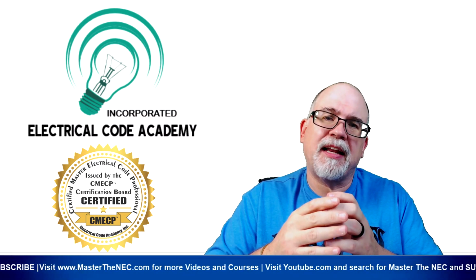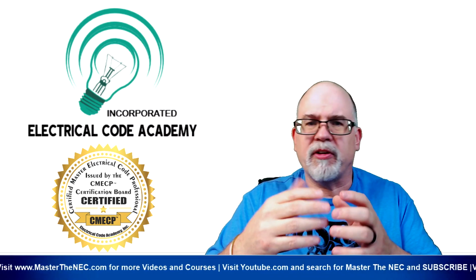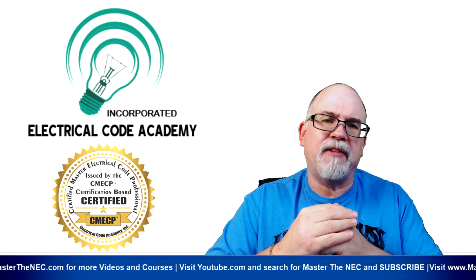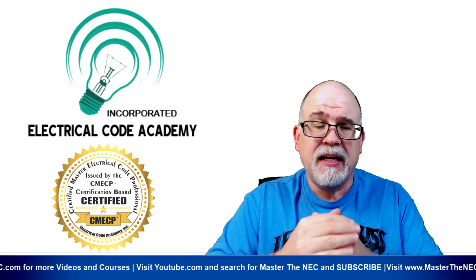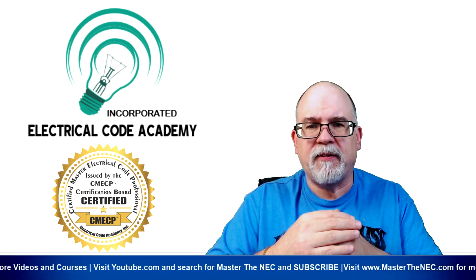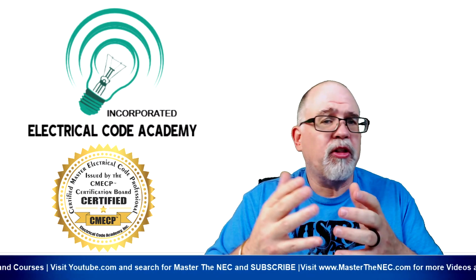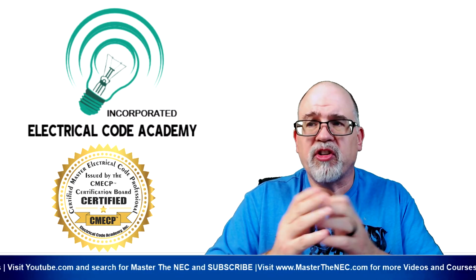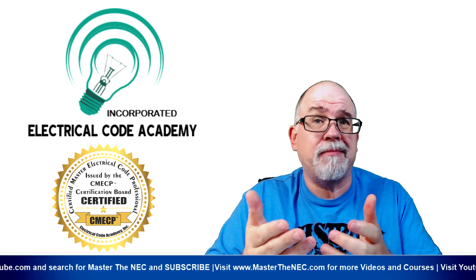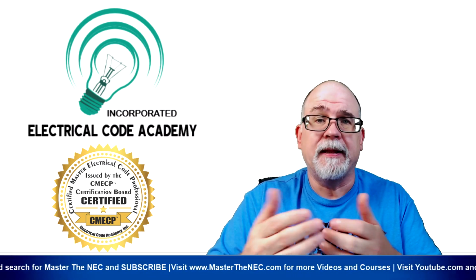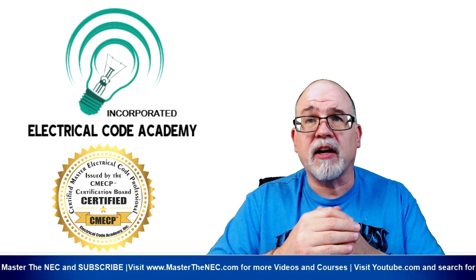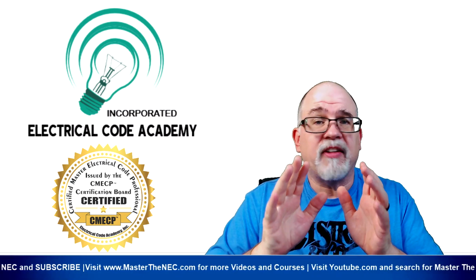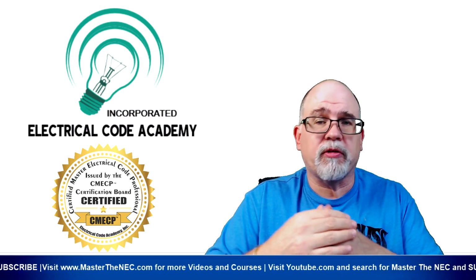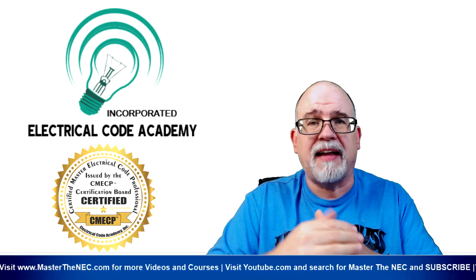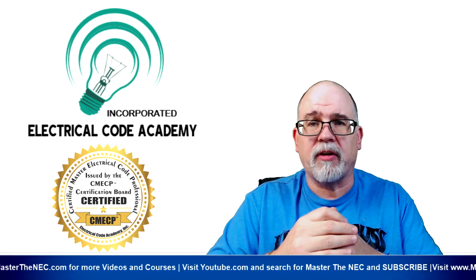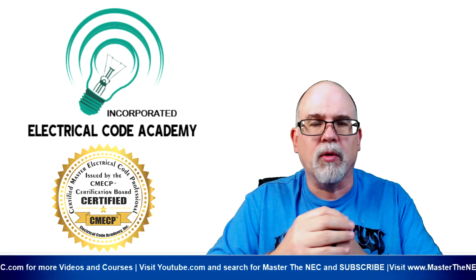I gave you some examples here of how they might work out for you in this scenario. If you don't know how to calculate the ampacity values for conductors based on adjustment and corrections, make sure you go watch that video on what's called Derating Demystified, because I cover all the things that deal with 310.15(B)(2)(a) and (B)(3)(a) and all of those things for adjustment and corrections, which could come into play here on secondary conductors depending on the ambient temperature or the number of current carrying conductors that you're dealing with. Okay, we did not size the grounded conductor in this episode, just the secondary conductors. We're going to cover the grounded conductor in a later episode, as well as the supply side bonding jumper, the system bonding jumper, and all those types of things. Don't worry, we're going to cover it all.